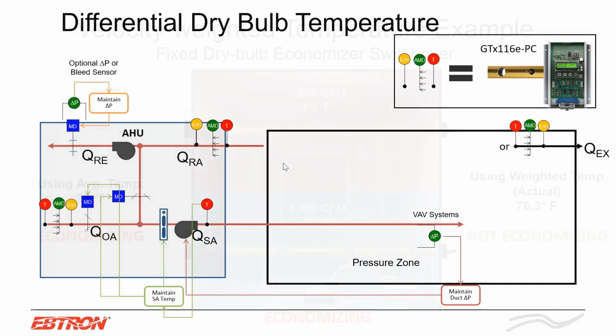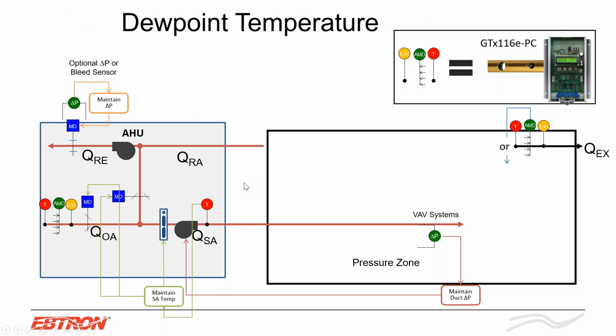Let's look at this, right? So again, this is another example of differential dry bulb temperature. It doesn't matter what type of economizer control strategy you're using, we can help you out with that. And again, I talked about ASHRAE standard 62.1, section 5.10, that on your systems, you have to be dehumidifying when the outdoor air dew point is above 60 degrees. We can do that just with your outside airflow meter and using our dew point reading, right?